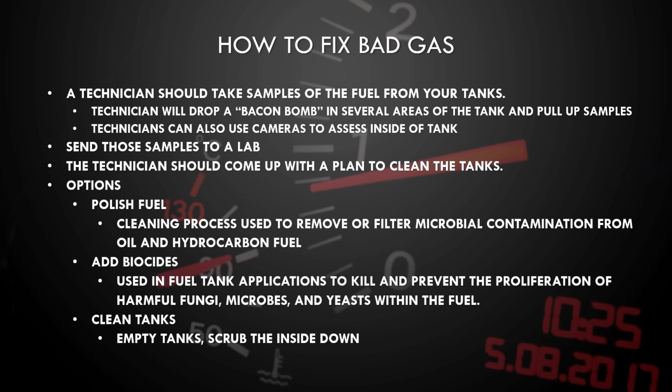Have them send these samples to a lab. They can do some analysis on the sample and make sure there's no contaminants in it. The technician should give you a plan for how to clean the tanks if there is indeed bad fuel in it. Some of your options are to polish the fuel, which is basically just pulling the fuel out, running it through a filtration system, and putting it right back into your tank.